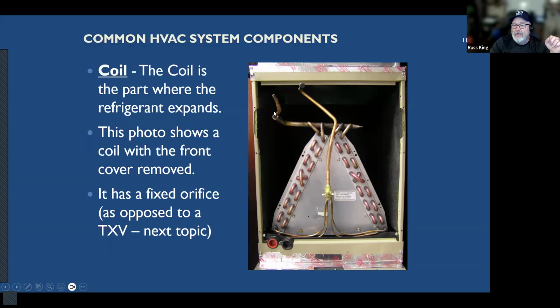So the liquid comes in here in this small tube. It goes through this little orifice. It starts to expand into a gas and it gets really, really cold. And then all this gas is collected in this big tube and sent out to the condenser where the heat is squeezed out of it. Okay. And we'll talk about that in a second. The compressor is what squeezes the gas. But anyways, this is the coil.